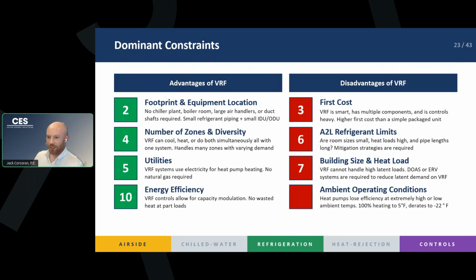I think actually this is a better slide to show things. So number 2 on our advantages of VRF on the left side, footprint equipment we just talked about, right? We have no chiller plants, no boiler rooms, no duct shafts, right? We're going to have small refrigerant piping and small indoor and outdoor units. This can be a powerful tool when your architect tells you there's not a lot of space.